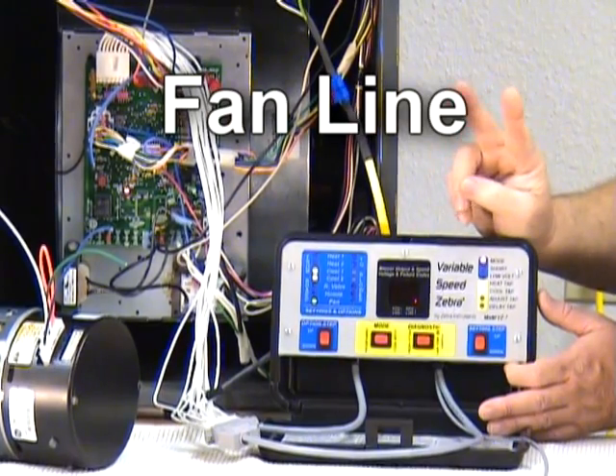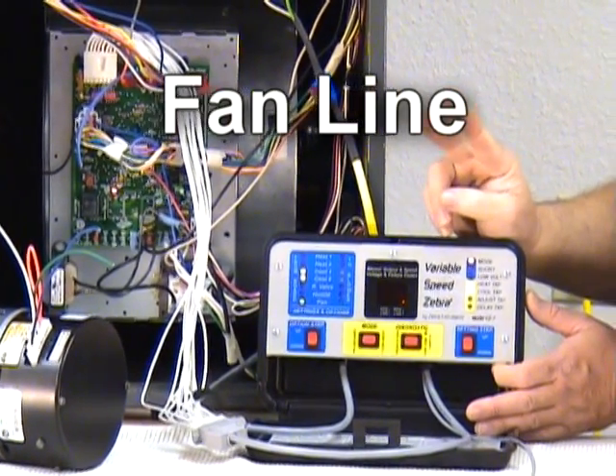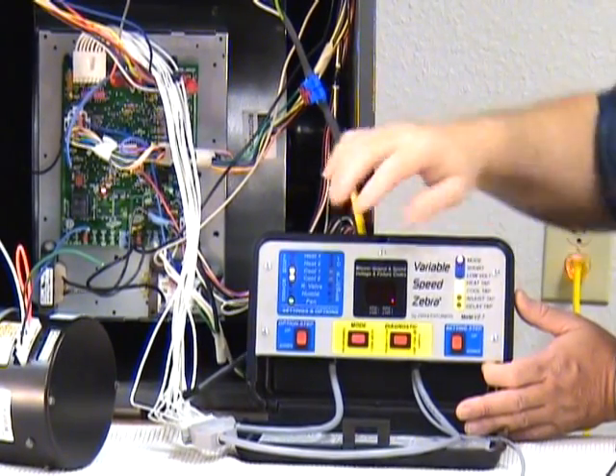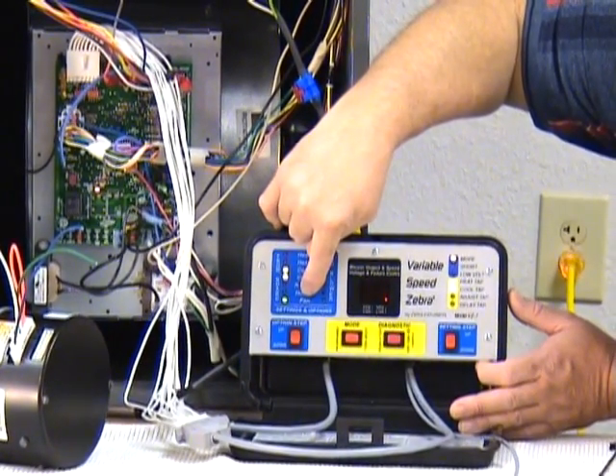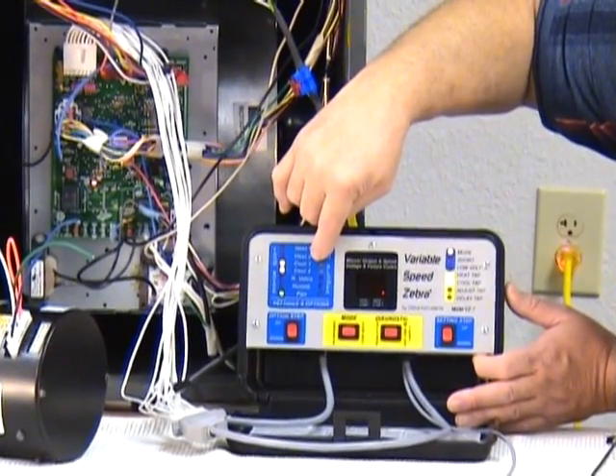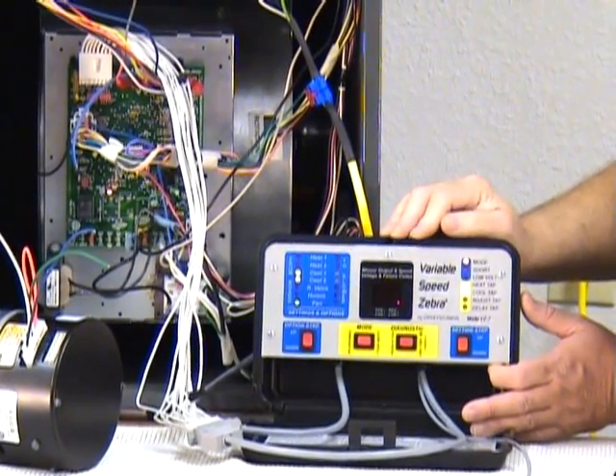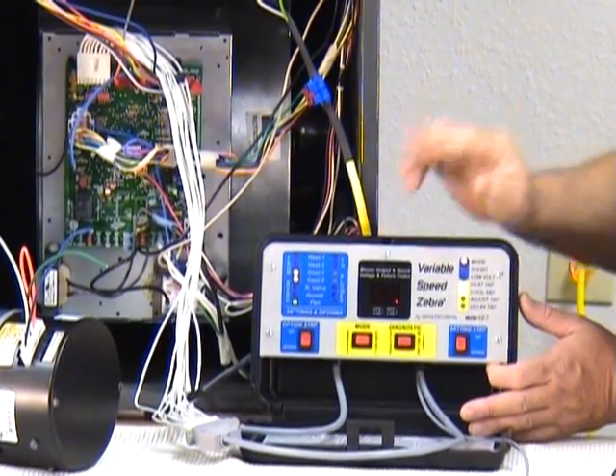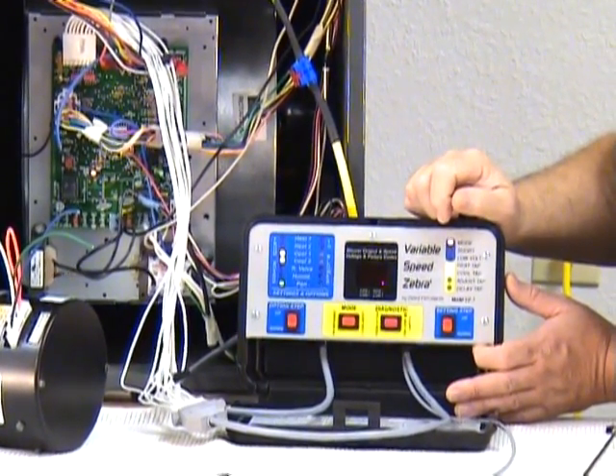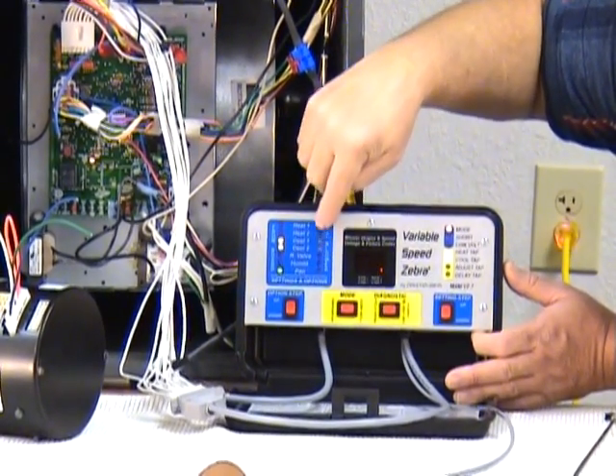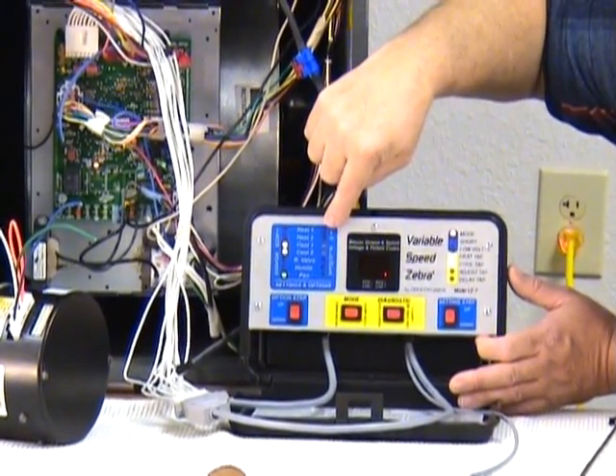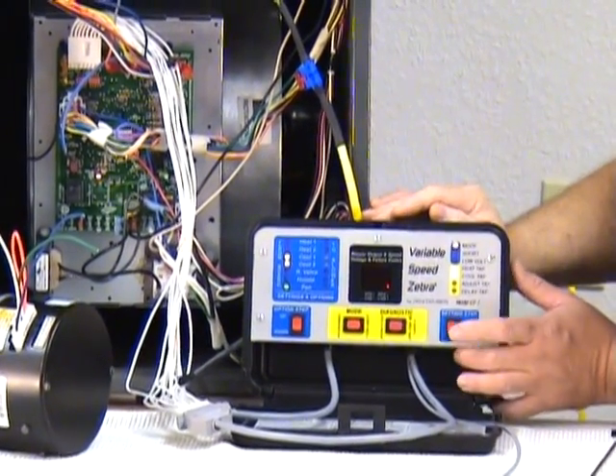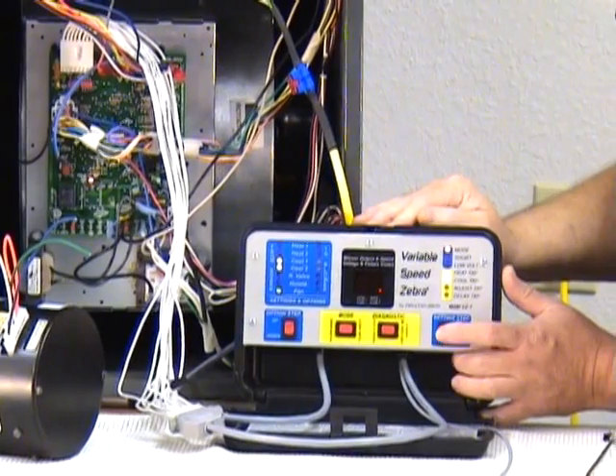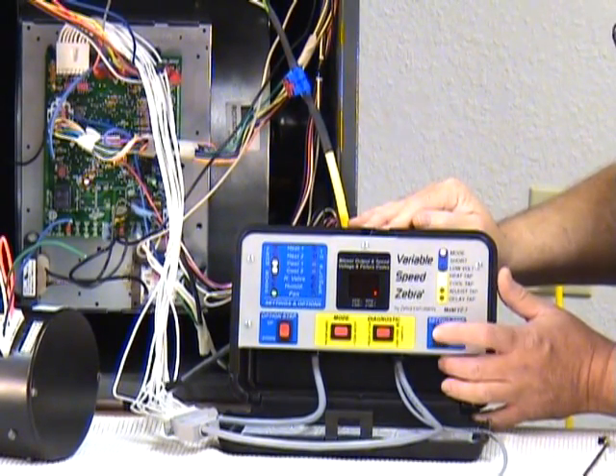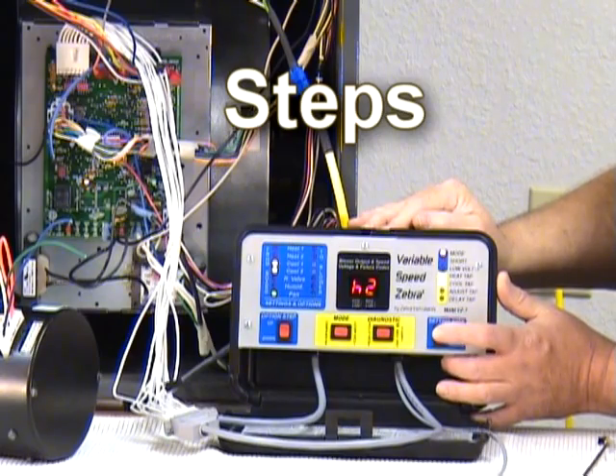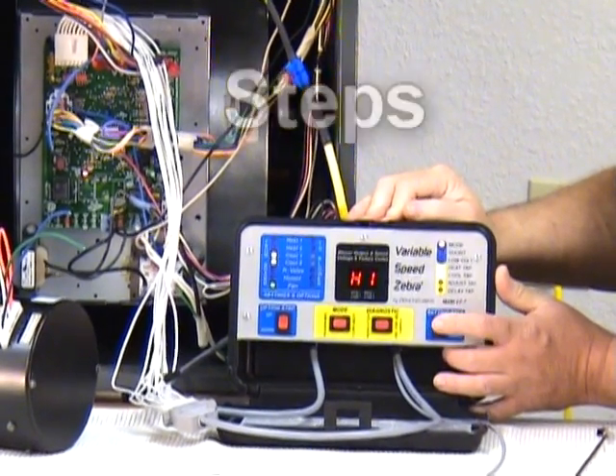Manufacturers use two different systems of sending those signals out. One of them always sends the fan line active anytime the motor is supposed to be active at all. Another one doesn't use that fan line active and only uses it when you're in the fan mode. The vast majority of them use the fan line on anytime any of these other settings are supposed to be turning the motor. So we're going to show you that way, but I'm going to show you that there's two different ways to access those settings. As you press the setting step switch up repeatedly, it's going to go through 10 cycles.